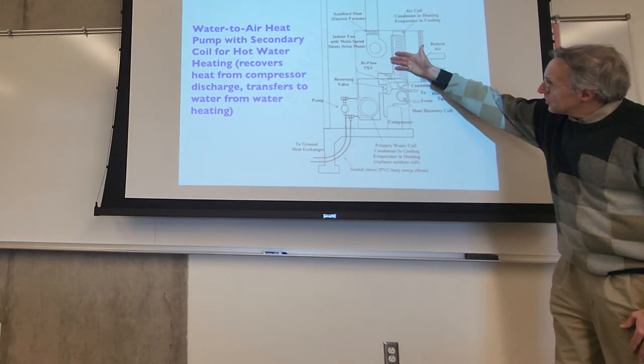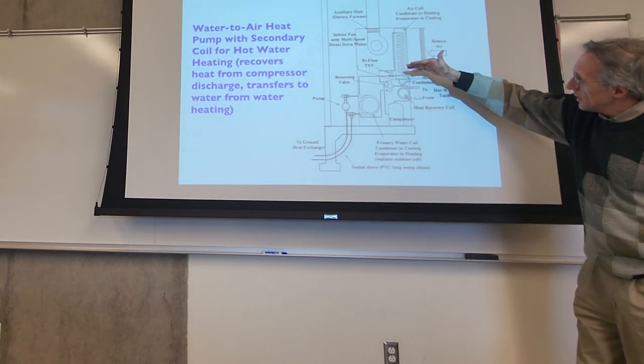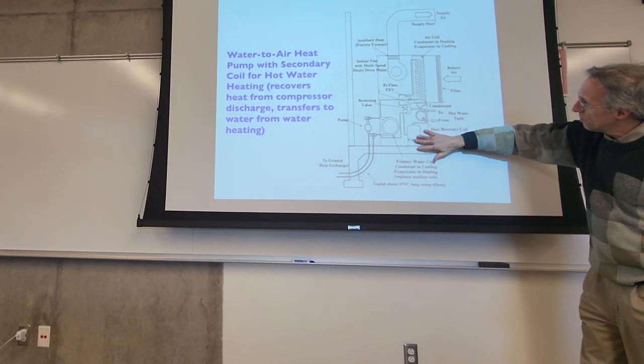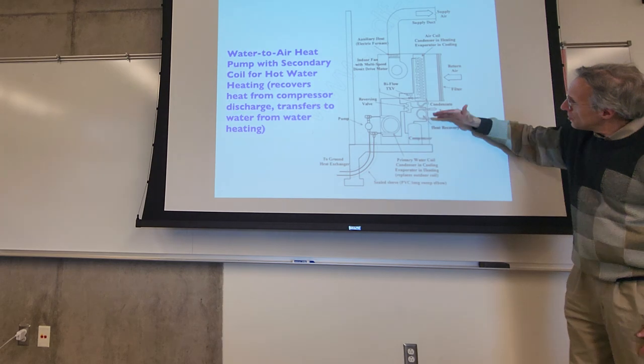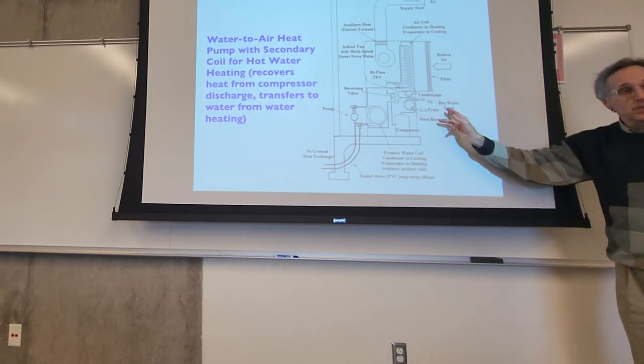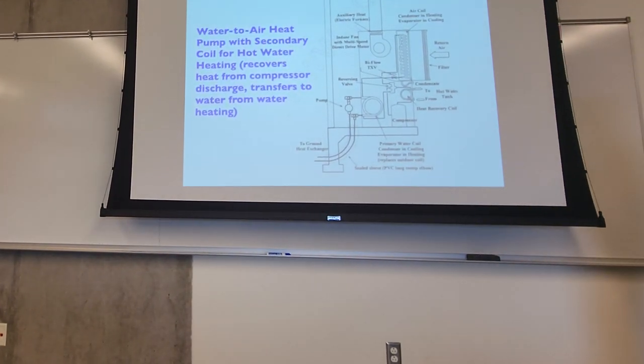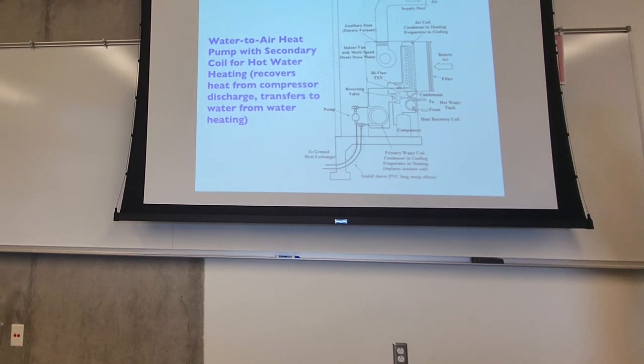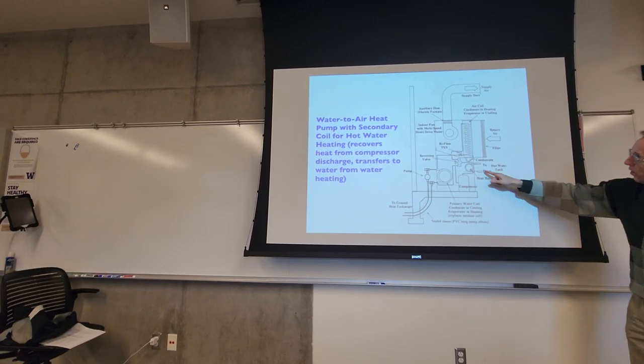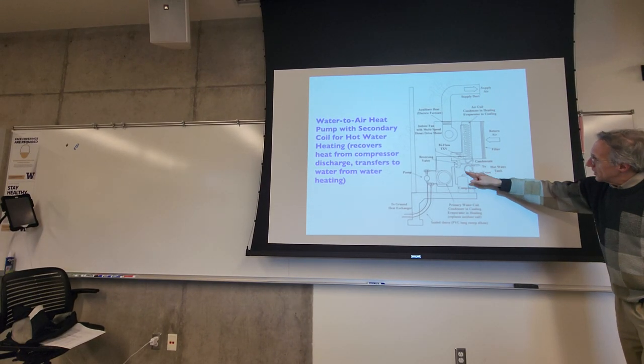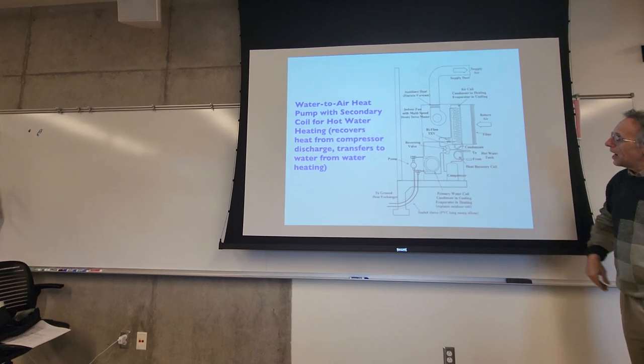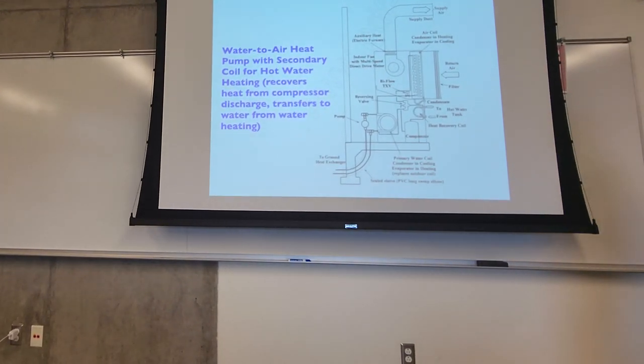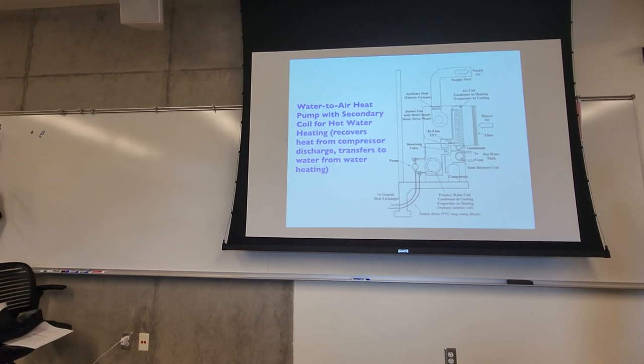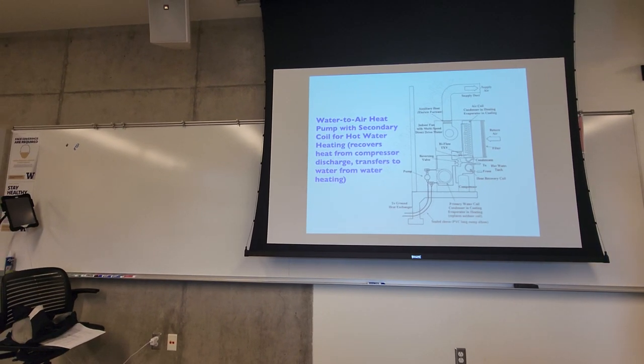And then the rest of the system, the evaporator, the throttling, the compressor, are mostly the same. This is a little more complicated because it also is heating water. The water heater, and so you have another little coil over here that heats water from the hot water heater. So very versatile and very energy efficient and very expensive in most places.